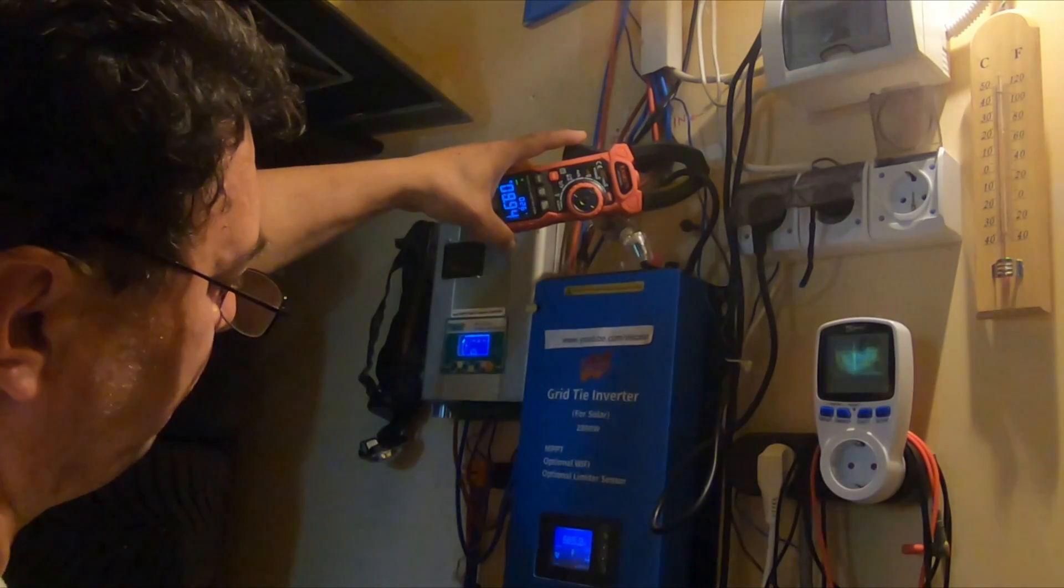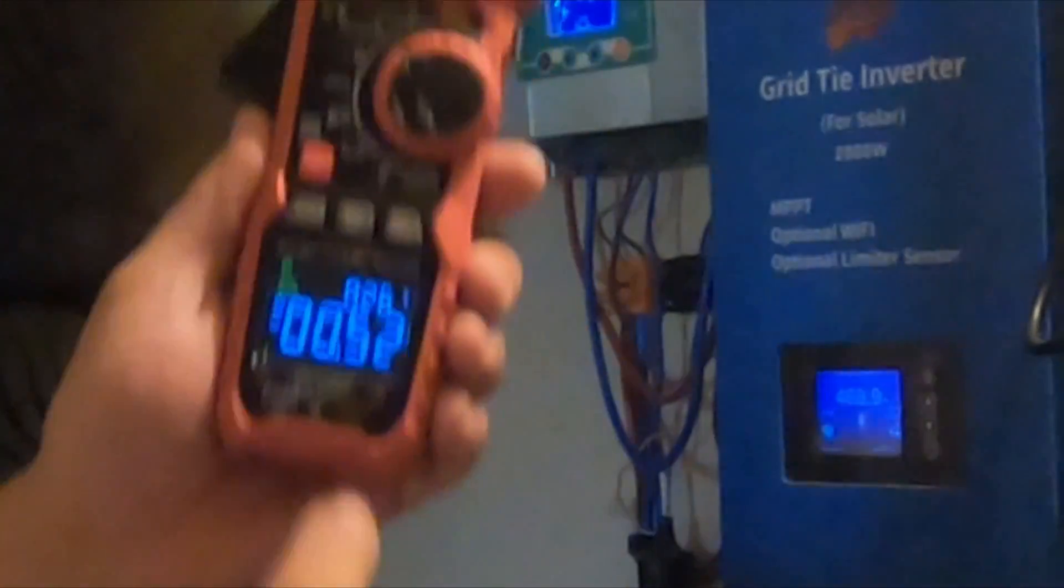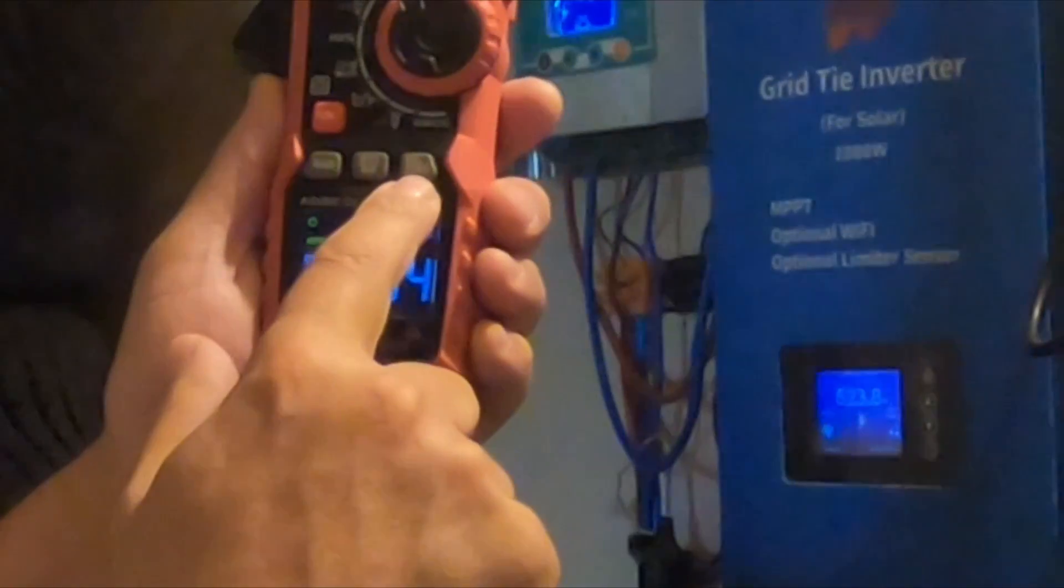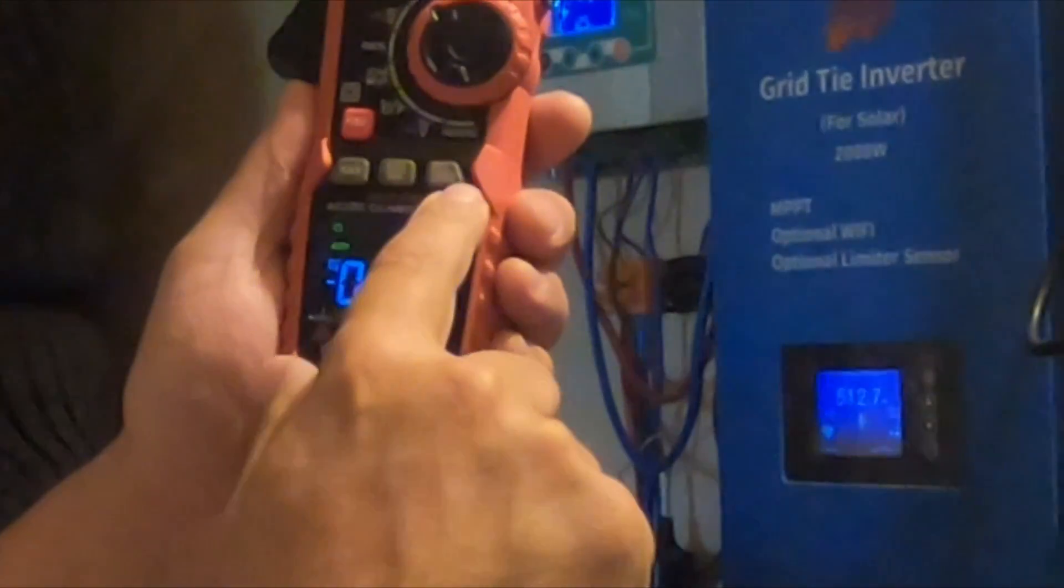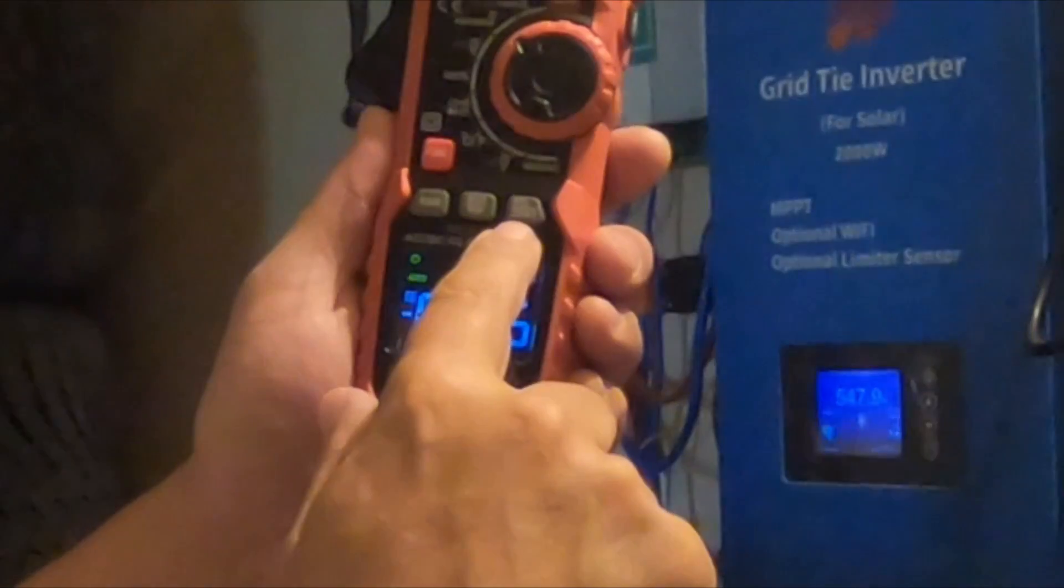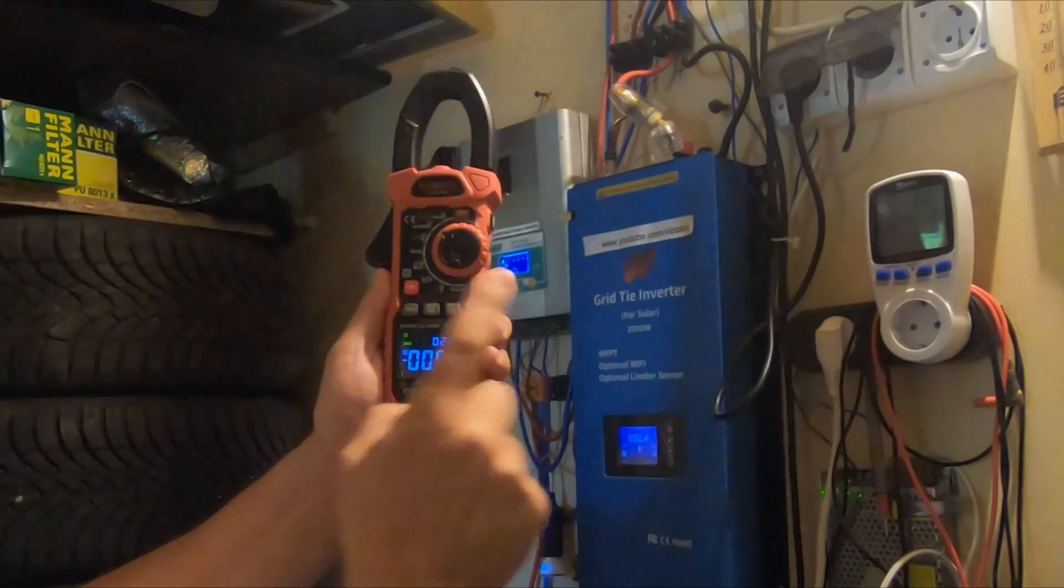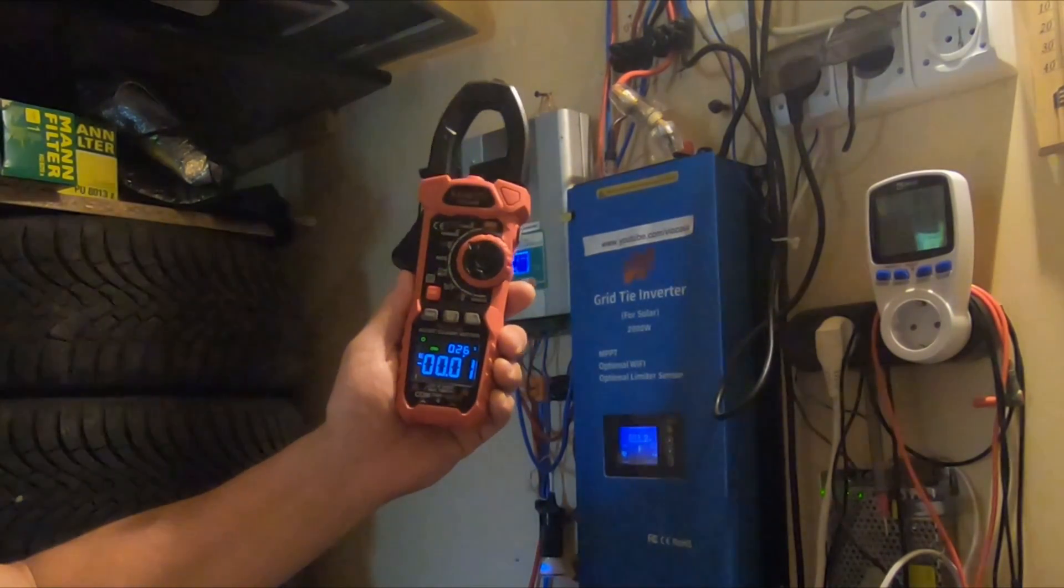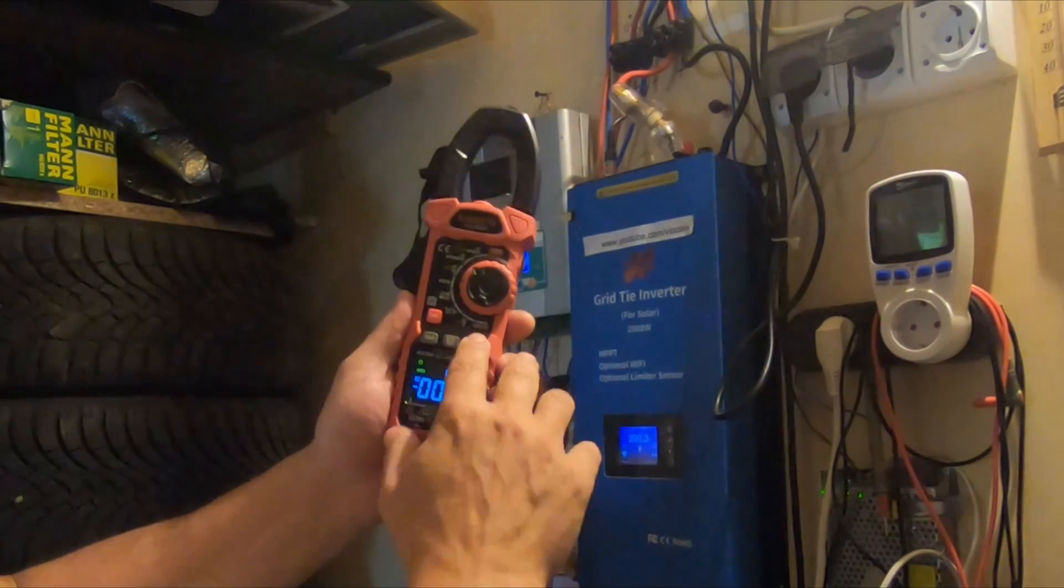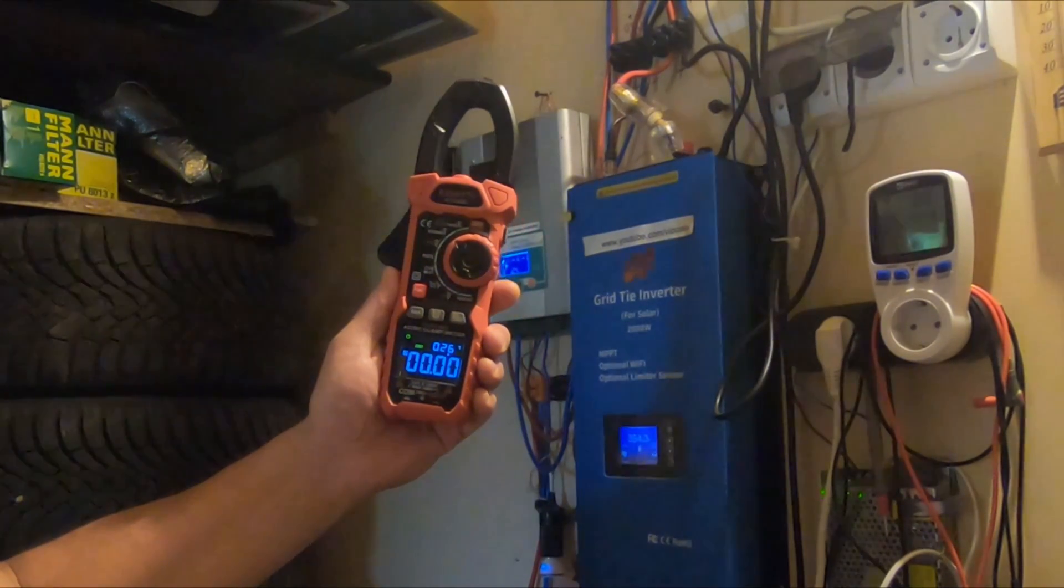Like I said before, this is because the sun. How can we fix this? You see, here on this clamp meter we have a switch which is REL and ZERO. That's relative and that's a zero. If we touch this before any measurement, then the clamp meter is going to zero.